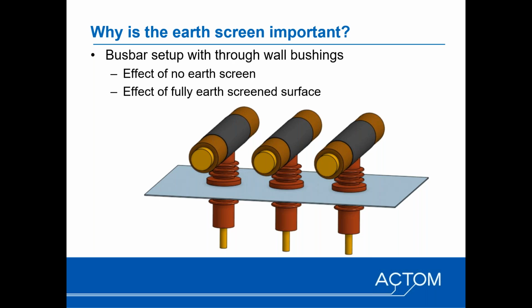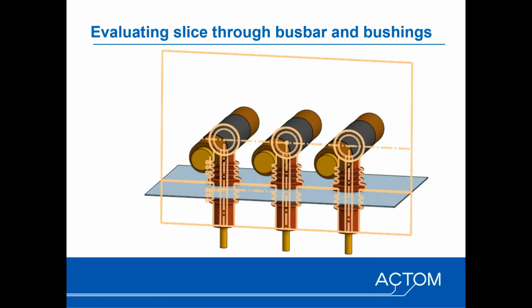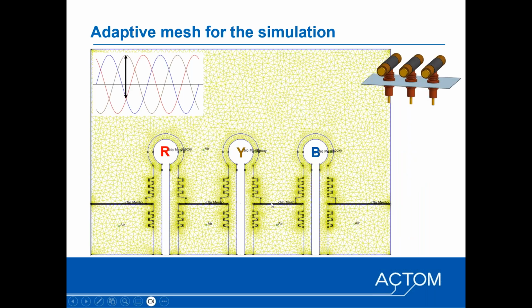To further illustrate the effect of the earth screen, I've got an example that I've done with a few field plots where we looked at a bus bar setup supported through insulators, basically through wall bushings on a metal plate, and evaluated the field plot and the effect of the voltage with the bus bars and insulator screened and without the earth screen applied. So if we take a slice through the setup, we get a 2D view of the bus bar setup, where we've got the 3 phases, the conductor running through the earth plate, which in this location is the earth plate, and then insulators supporting the bus bars.